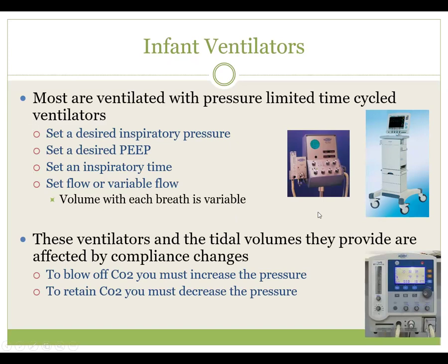You set inspiratory pressure, you set PEEP, you set inspiratory time, and you set flow. Inspiratory time and expiratory time together gave us our rate. These were infant only ventilators. The volume with each breath was variable. Now ventilators will span neonatal through adult. Microprocessor ventilators, all three of the big ones in our lab, will do that.